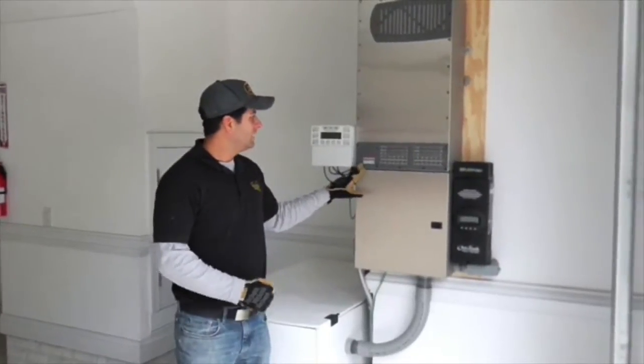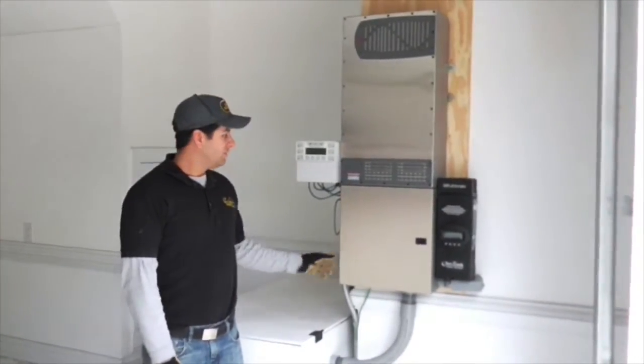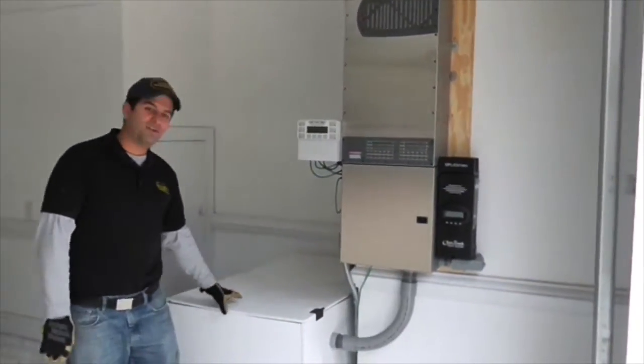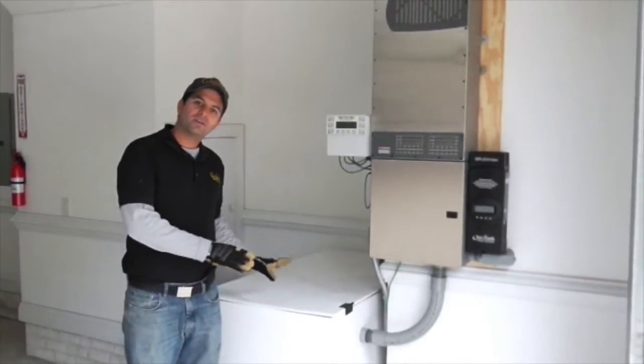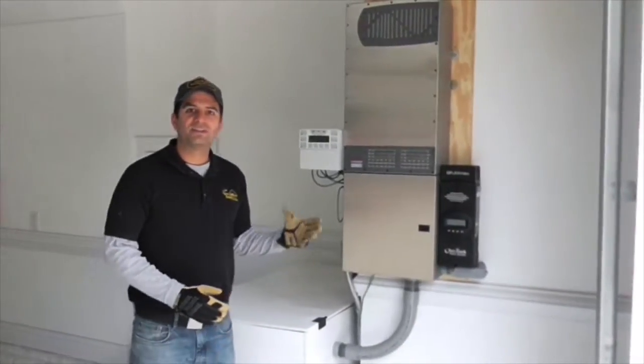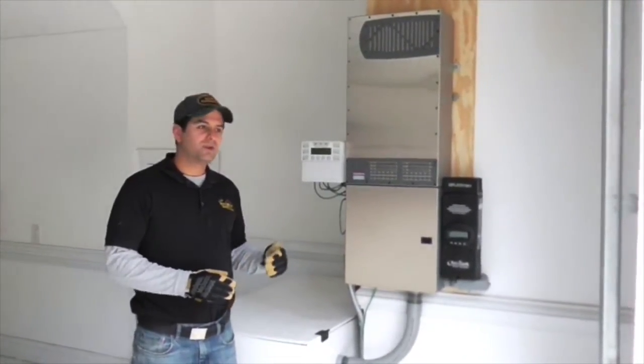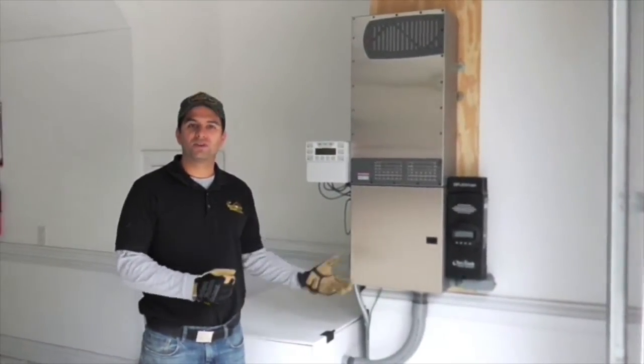We have a Radian 8,000 watt Outback inverter. This is the GS Load Center and we have a battery bank here. It's a 220 amp hour battery bank, rather small battery bank. The whole idea of this job was to give the customer a battery system with solar production if the grid goes down to power her critical loads.